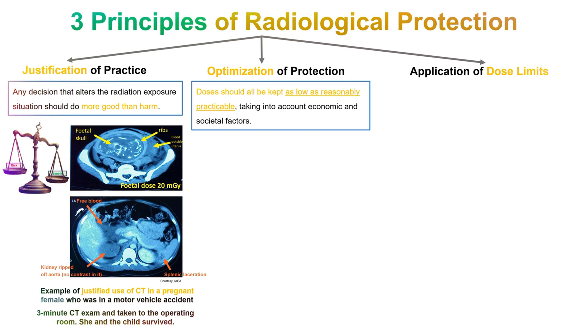Here are some examples. The general public would generally be around the vicinity of a radiation environment, such as immediately outside of a CT scan room or present immediately on the other side of the wall of an interventional radiology room — this includes hospital staff who are not radiation workers. For patients who undergo medical exposures for diagnostic and therapeutic purposes, such as a chest x-ray or a head CT scan, extra radiation dose can be reduced by proper collimation, exposing only the region of clinical interest.